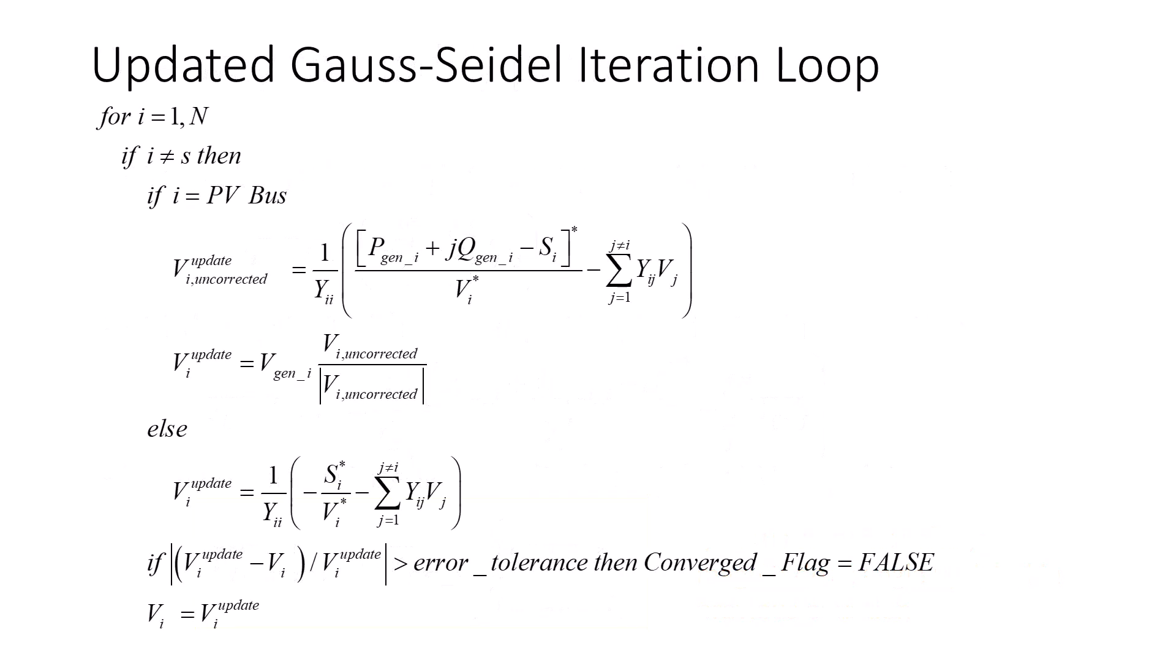An updated Gauss-Seidel iteration loop logic for a system with loads, generators, and a single-swing bus is shown here. We simply need to set up an update loop to iterate over each bus, which is not the source bus. We then apply the appropriate formulas on the previous slide, depending on whether we have a PV bus or a PQ bus. As each bus voltage is updated, we check for convergence, and if convergence for any bus fails, we set the convergence flag to false.